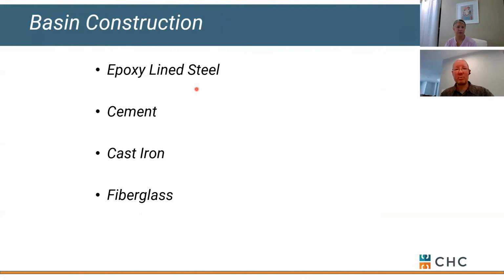All right, let's move on to basins. We're doing okay for time. Let's see how this plays out. We have some options for our basins, and I'm going to run you through a quick example. One thing that comes up all the time is how do I size a basin? How do I know the diameter and the depth, and how do I get all this to work? Normally we have 2 pumps, you have some floats. We have to make sure there's enough usable water inside a basin.